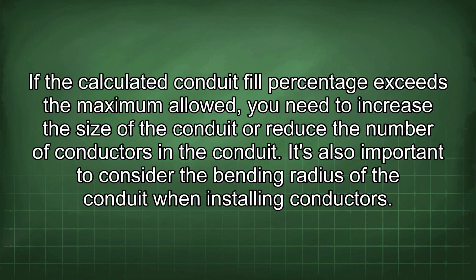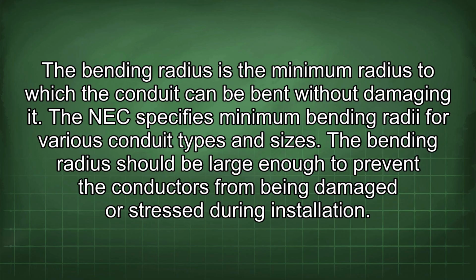If the calculated conduit fill percentage exceeds the maximum allowed, you need to increase the size of the conduit or reduce the number of conductors in the conduit. It's also important to consider the bending radius of the conduit when installing conductors. The bending radius is the minimum radius to which the conduit can be bent without damaging it. The NEC specifies minimum bending radii for various conduit types and sizes. The bending radius should be large enough to prevent the conductors from being damaged or stressed during installation.